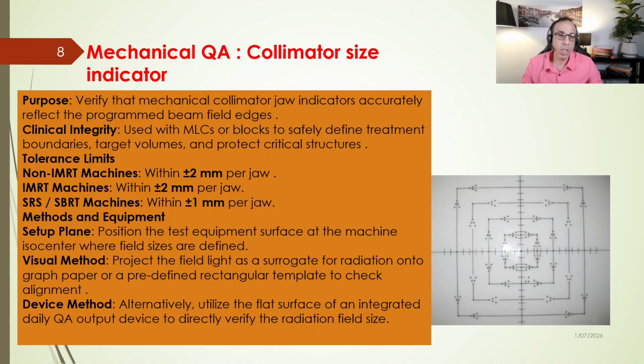On this slide, we focus on the verification of the machine collimator jaw indicator. The core purpose here is to confirm that these physical indicators, the field size indicators, which show the jaw positions, accurately match our programmed beam field edges. Maintaining this accuracy is vital for clinical integrity because the jaws work with MLCs or blocks to strictly define our treatment boundaries, cover target volumes, and shield nearby critical structures. Looking at our tolerance limits, non-IMRT and standard IMRT machines allow a variance within plus minus 2 millimeter per jaw.